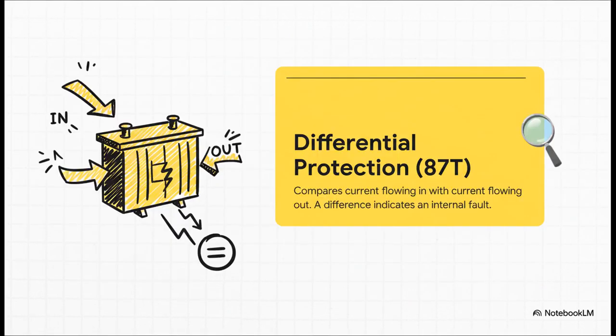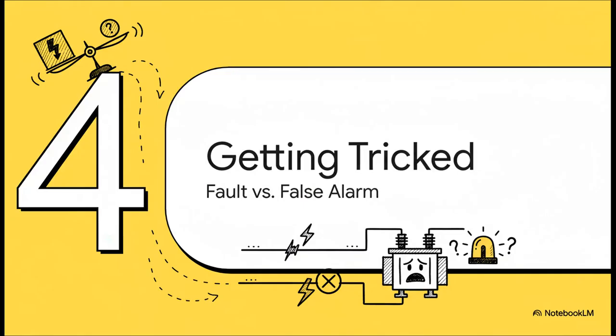Okay, so this principle has a name. It's called differential protection, or 87T if you're an engineer. Here's how it works. A special device, a relay, is constantly measuring the current flowing into the transformer and comparing it to the current flowing out. They should be perfectly balanced. What goes in must come out. If they're not balanced, if there's a difference, well, that means current is leaking out somewhere inside that transformer. And that can only mean one thing. There's a fault.